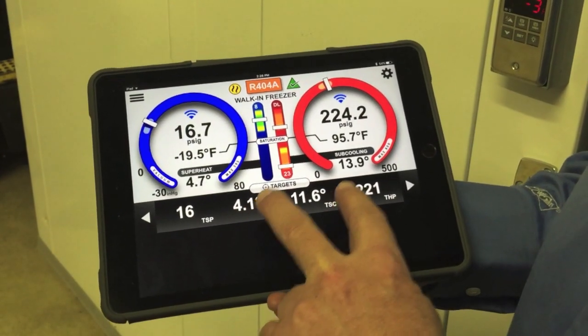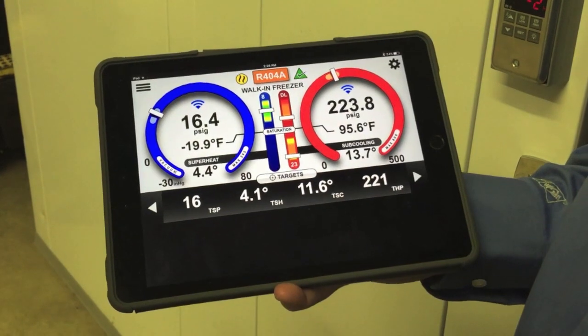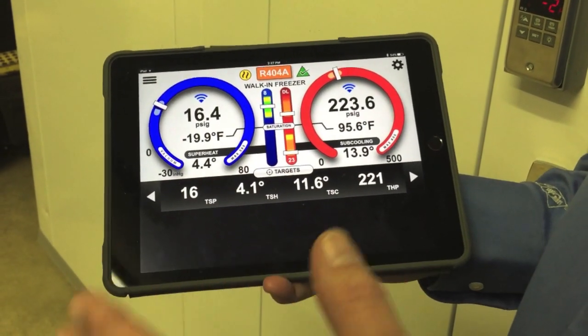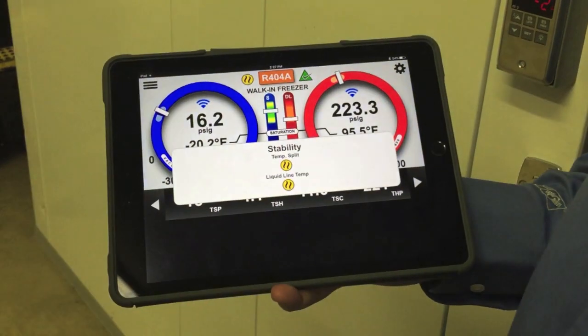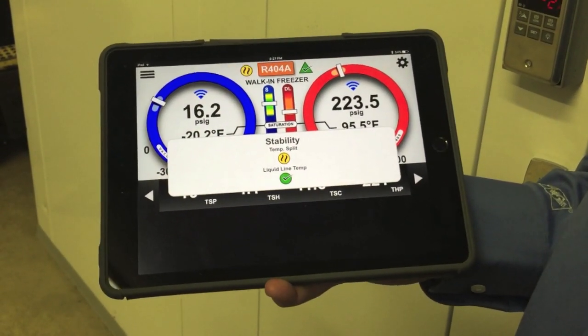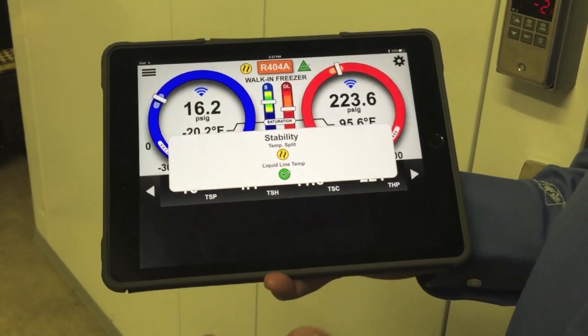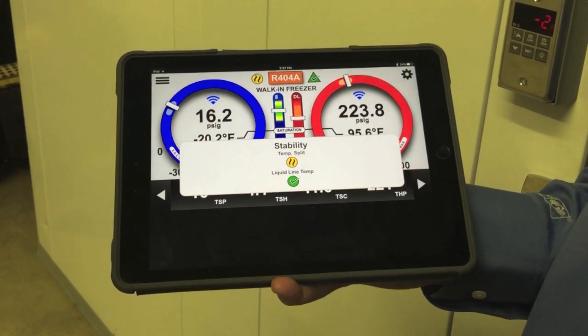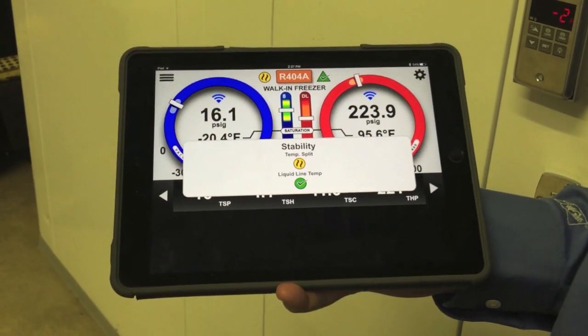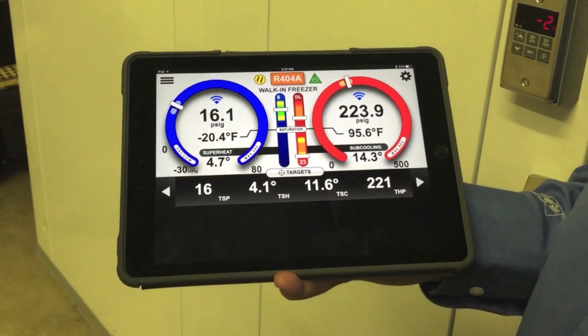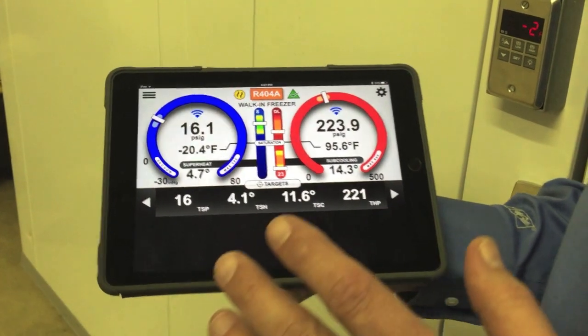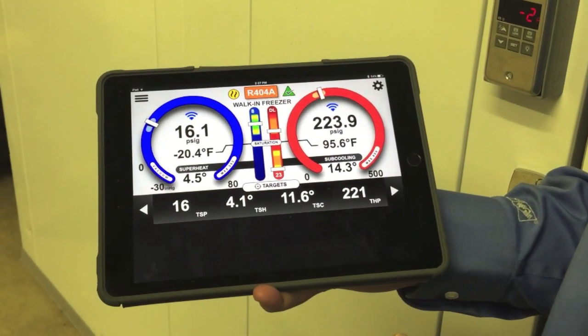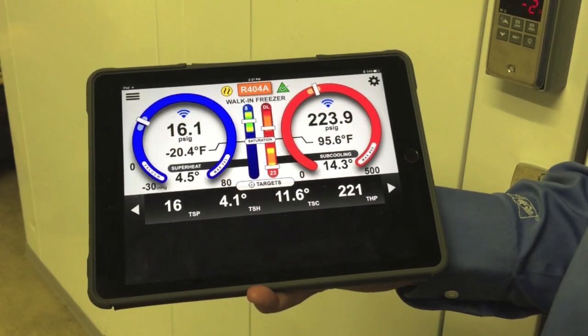The target superheat and target subcooling came from our benchmark when we commissioned this piece of equipment. We stored that information and now we're looking for it to operate basically the way it was the day we installed it. We're waiting for the system to stabilize — this is the stability indicator. We're looking for a stable liquid line temperature and a stable temperature split. With refrigeration equipment, you cannot evaluate the system performance until you're close to the box temperature. If you're 10 degrees or more above box temperature, there's just too much load on the box to get good readings. Now we're able to pull that data down. If you're a refrigeration technician these numbers look really good, but if you're an air conditioning technician you might be adding gas just to get the suction pressure up to 70, like every other piece of equipment you work on.